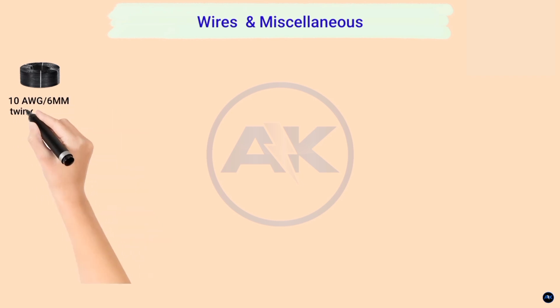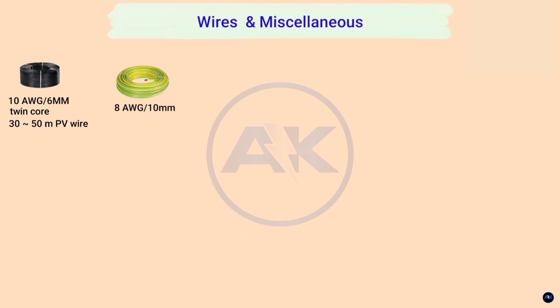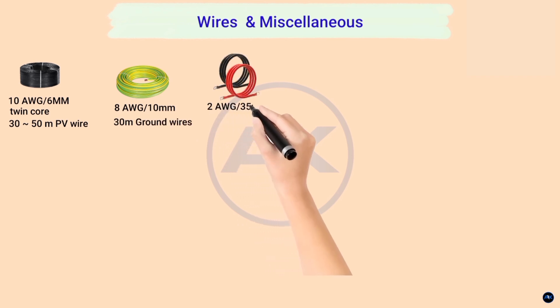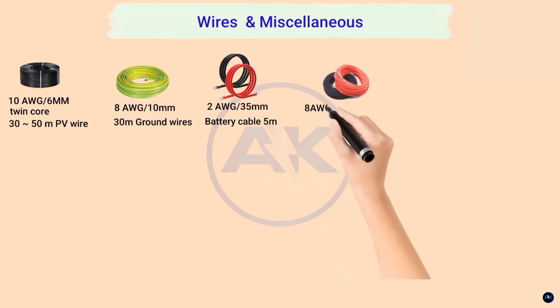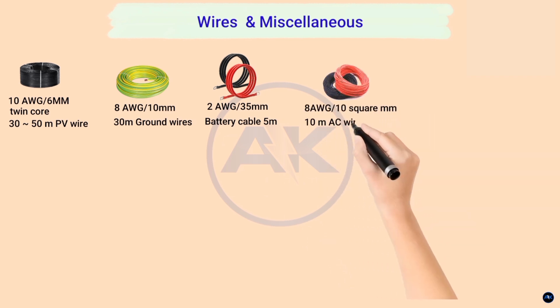Wires, cables and miscellaneous. First on the list we have 10 AWG, 6 square millimeter twin core PV wire, 30 to 50 meters, but the length should be calculated based on the distance between your PV array and the main system. But I would suggest at least 30 meters. Next is the ground wire, it has to be 8 AWG or 10 square millimeter, at least 30 meters. Third is the 2 AWG, 35 square millimeter battery cable, at least 5 meters each, with terminal lugs, and 8 AWG or 10 square millimeter, 10 meters of THHN AC wires.